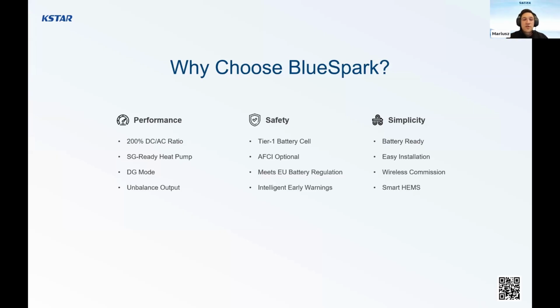We meet the EU battery regulation, with intelligent early warnings, like our BMS, for example. If we connect plus and minus to make a short circuit, all of the batteries contain the BMS, and if the battery detects the short circuit, it will just disconnect, and that's all. So there will be no risky situation. But for example, if you are stacking high voltage solutions without a BMS at the module level, it can be risky because there is no BMS, there are no safety devices. The simplicity: the battery is ready for upselling, easy installation, wireless commissioning, and smart HEMS.